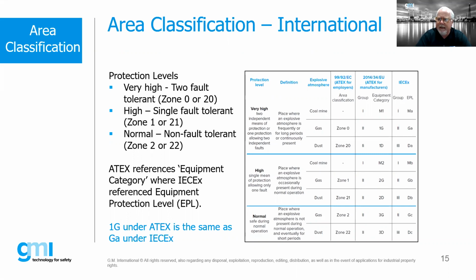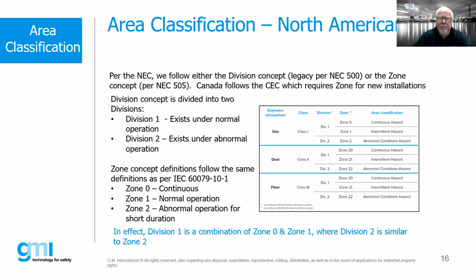So now we understand a little bit about zones. This should hopefully give us a little bit more understanding of what we have to put on our equipment and making sure that it's suitable for that environment. In the North American world, I realize that many of you don't deal with US installations, but we actually have in the United States a legacy class and division system. And we've also adopted within the National Electric Code, within NEC 505, which is basically our wiring regulations, the zone concept. So a little bit of a comparison, if you will.